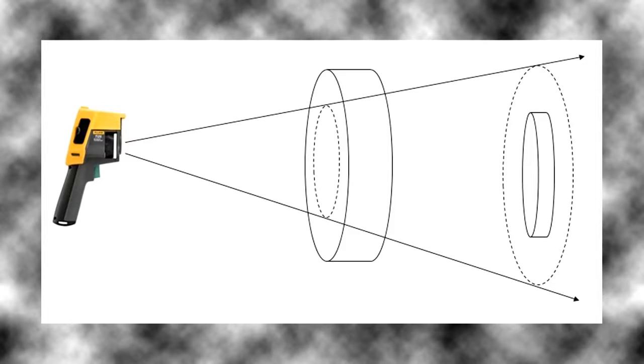In our graphic, you see that the first target is bigger than the spot size, which is the preferable situation. The measurement area is contained completely on the target.